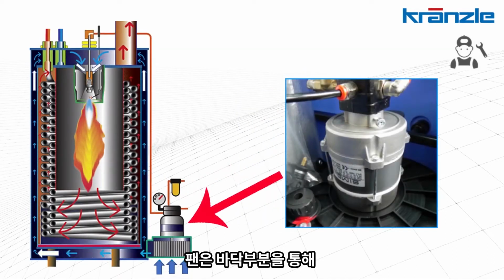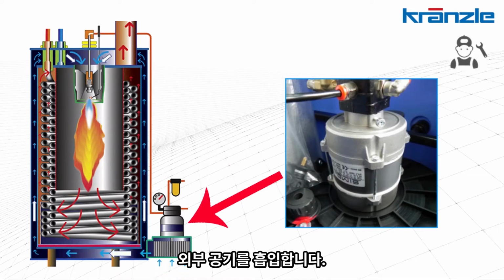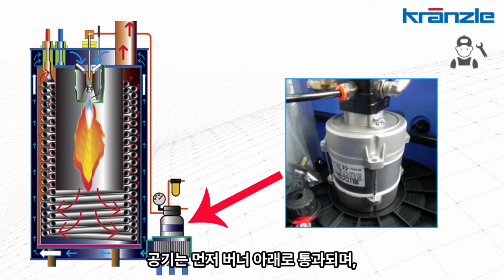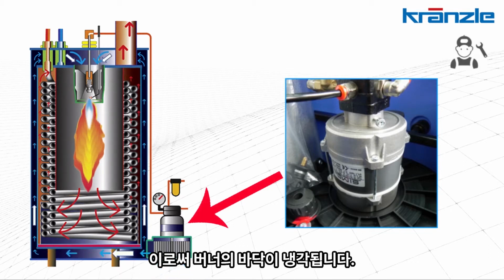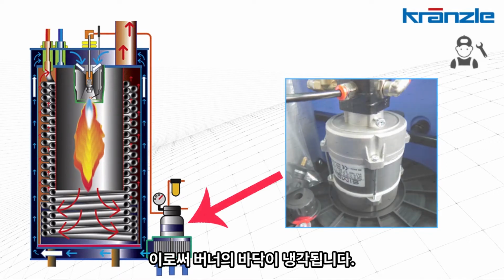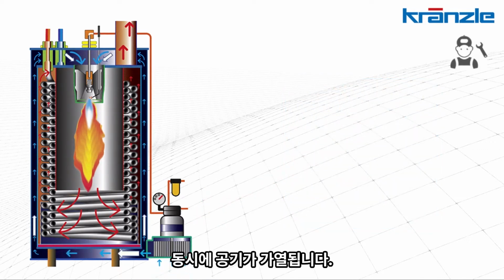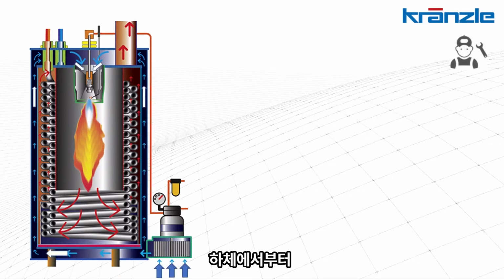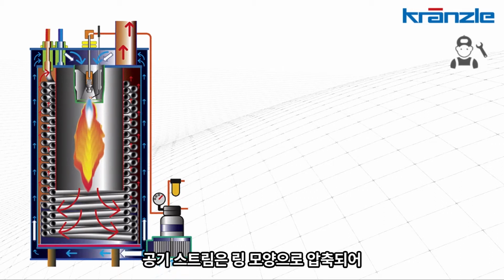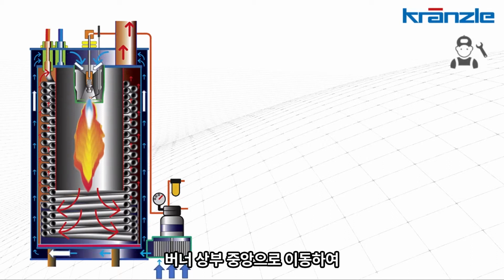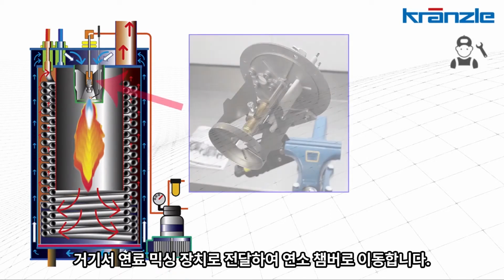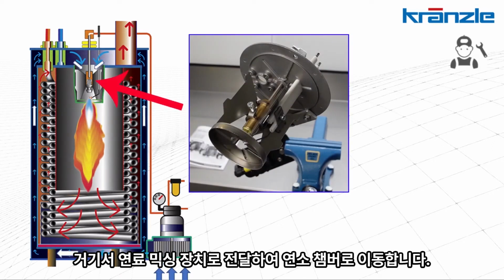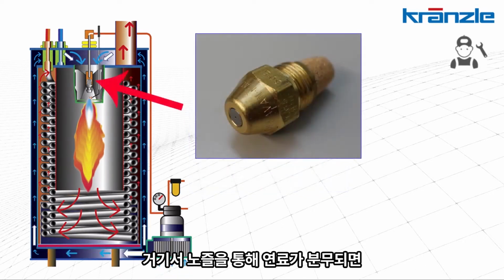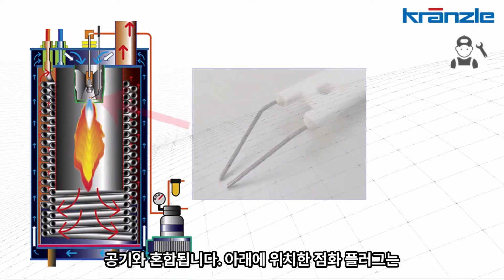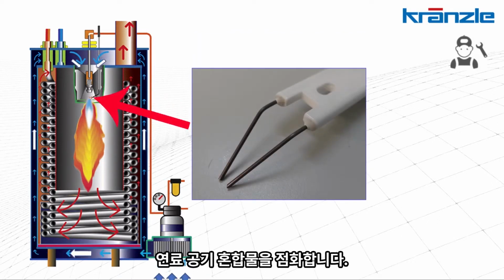A fan draws in the cold fresh air through the bottom of the unit. The air is first forced through the underside, thereby cooling the bottom of the burner. This simultaneously causes the airstream to heat up. From the underbody, the airstream is pressed into a ring shape via the intermediate mantle into the upper collecting chamber and from there into the mixing device to the combustion chamber. There, finely atomized fuel is injected via a nozzle and mixed with the air. The electrodes positioned below ignite the fuel-air mixture.